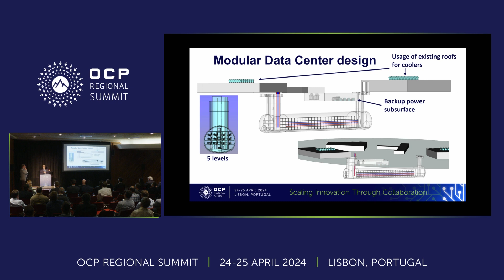So we choose the dense solution without raised floor, without ceiling, without hot and cold aisles. It's a door heat exchanger, so everywhere is a cool environment. And the temperatures we use at peak times, it's 34 degrees inlet water and 44 outlet.